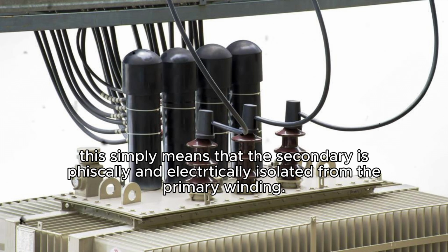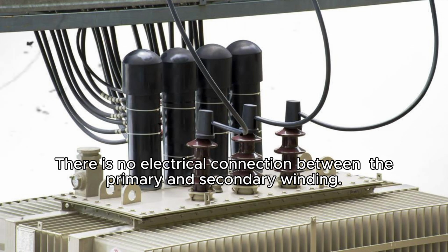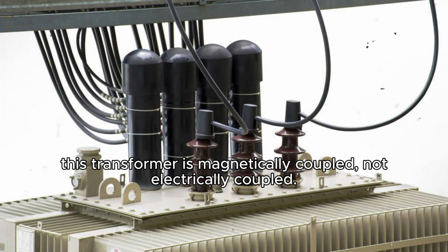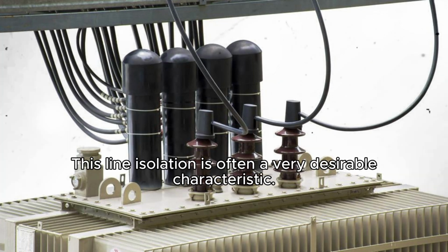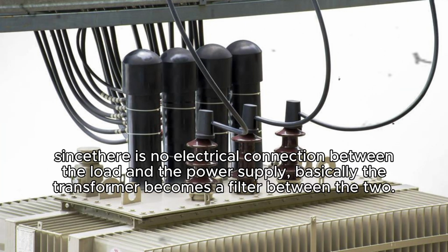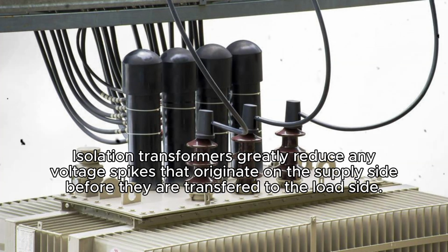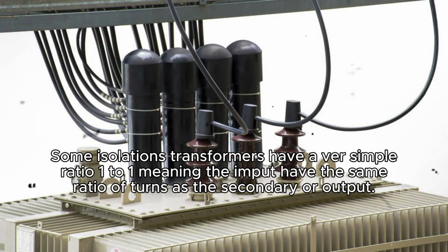Isolation transformers. This simply means that the secondary is physically and electrically isolated from the primary winding. There is no electrical connection between the primary and secondary winding. This transformer is magnetically coupled, not electrically coupled. This line isolation is often a very desirable characteristic. Since there is no electrical connection between the load and the power supply, basically the transformer becomes a filter between the two. Isolation transformers greatly reduce any voltage spikes that originate on the supply side before they are transferred to the load side. Some isolation transformers have a very simple ratio of 1:1, meaning the input has the same ratio of turns as the secondary or output.